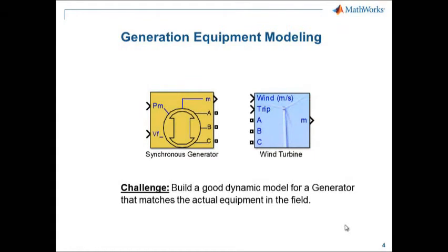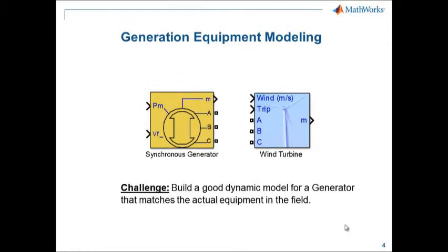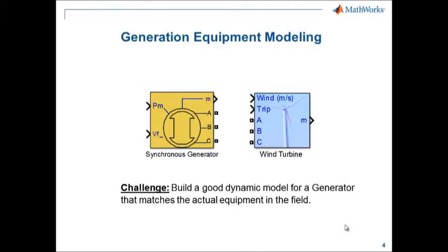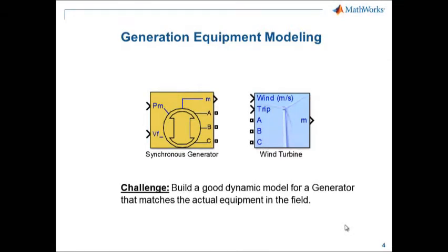They are known as the offline tests and the online tests. In case of offline tests, you would typically perform voltage step tests on these generator units and then try to estimate their parameters and build computer simulation models using that data. Now, as compared to that, in case of online tests, you could be looking at the real disturbance data that is being measured in the field using digital fault recorders, or we could be looking at the synchrophasor data, which is being gathered from the phasor measurement units, right? Now, there are cases where online disturbances could help you reveal the parameters of the equipment that wouldn't necessarily be obtained from the offline test.